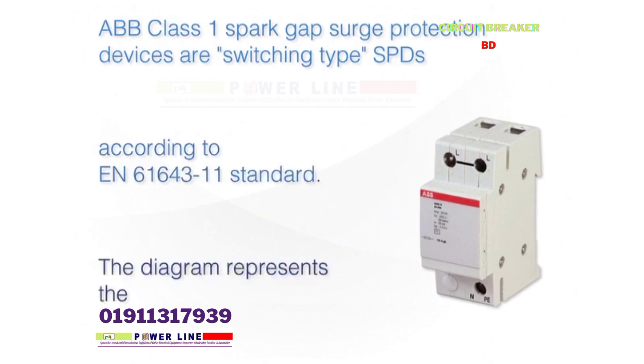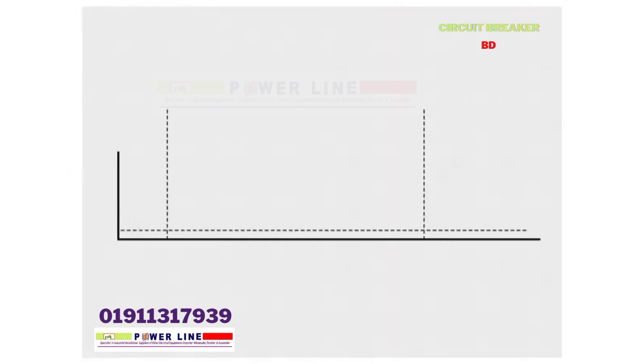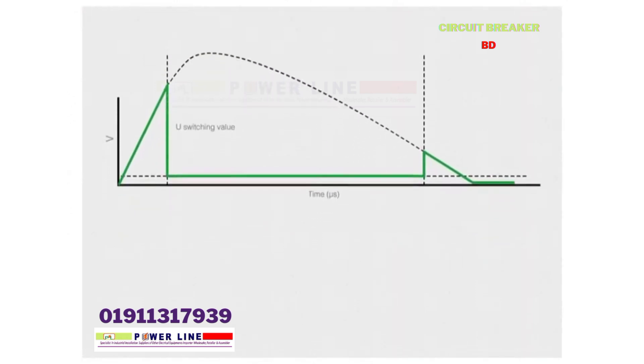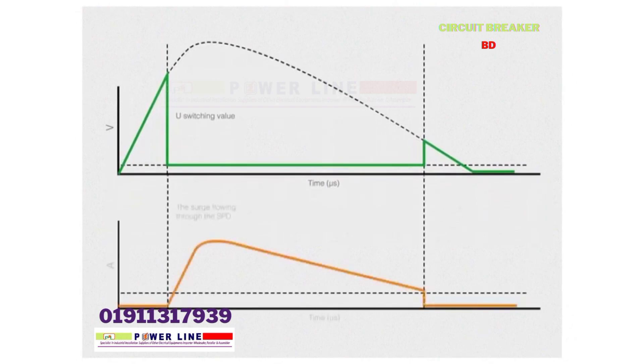The diagram represents the tripping characteristic of these devices. As seen from the figure, at the occurrence of a certain level of overvoltage — the switching value — the voltage across the module collapses suddenly to just a few volts, the value corresponding to the arc voltage.